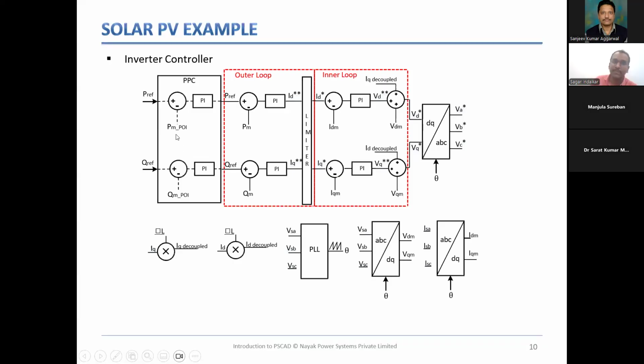fast devices. So, your inverter controller, I will not discuss in much detail. You have already studied inverter control. You know what ABC to DQ transformation is, and what reference frame theory is. Then I will just brief it to you. The inverter controller will basically ask for a reference for whatever P and Q is to be generated. It will measure that P and Q, take out the error, pass it through a PI controller, and then perform the park transformation. Ultimately, it will give us the direct axis and quadrature axis current components, ID and IQ.